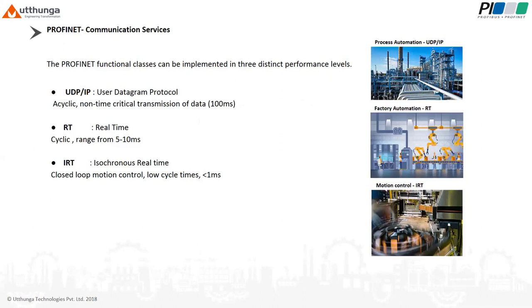Communication services. In PROFINET, communication services contain UDP/IP, RT, and IRT. UDP/IP is User Datagram Protocol. It's an open communication via Ethernet. It is transmitted in 100 milliseconds, mostly acyclic, non-time-critical transmission of data; parameterization, configuration, and diagnostics come under UDP/IP. While with real-time RT, cycle times can be realized in the range of 5 to 10 milliseconds. PROFINET real-time is fully compatible with TCP/IP standards without any restrictions. All PROFINET devices must support RT, which usually means around 250 microseconds to 10 milliseconds.